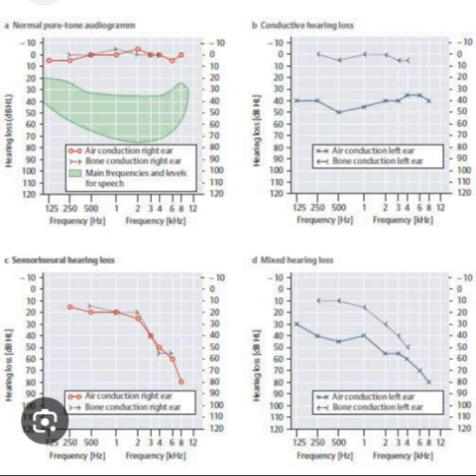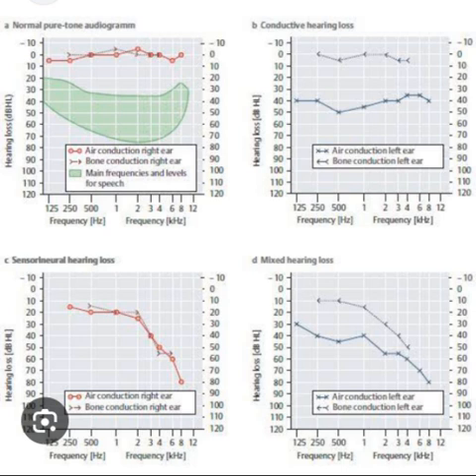After collecting hearing data, pure tone thresholds at each frequency are displayed on an audiogram. The x-axis represents the frequency of sound in hertz and the y-axis represents the inverted intensity of sound in decibels hearing level. The American Speech-Language-Hearing Association (ASHA) sets forth guidelines for the standardization of audiogram symbols. When color is available, red indicates the right ear and blue indicates the left ear; the less-than and greater-than symbols for left and right ear thresholds were chosen to vaguely resemble a patient's ears facing the interpreter.